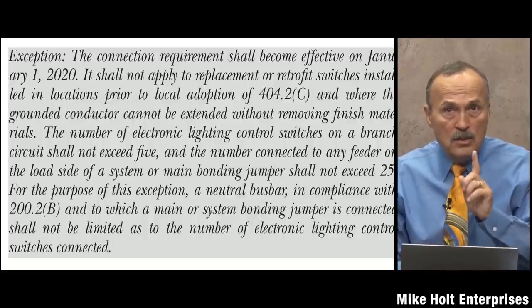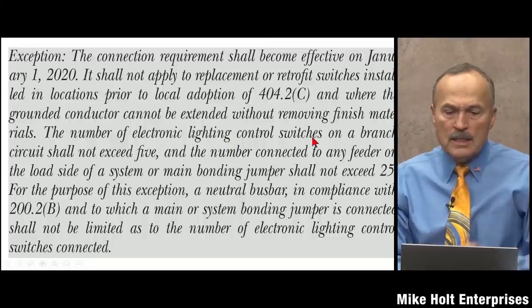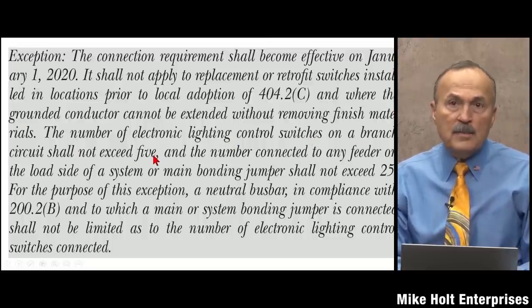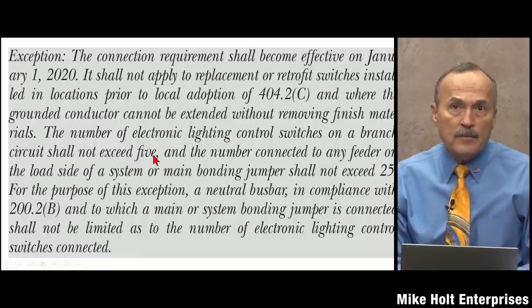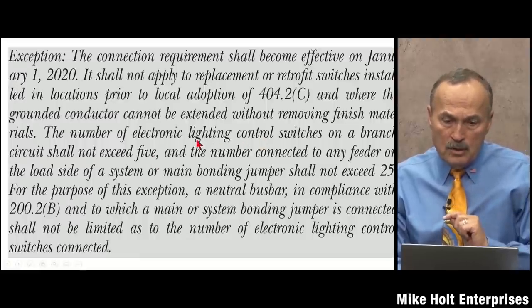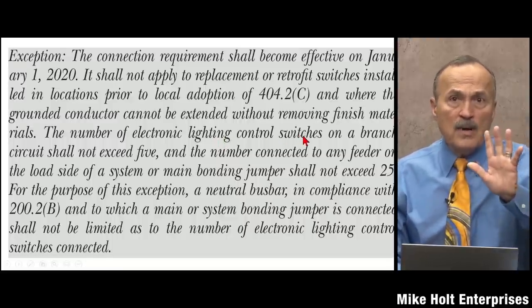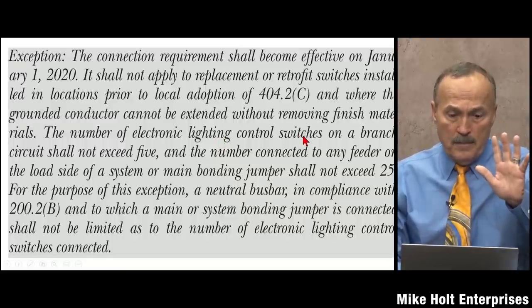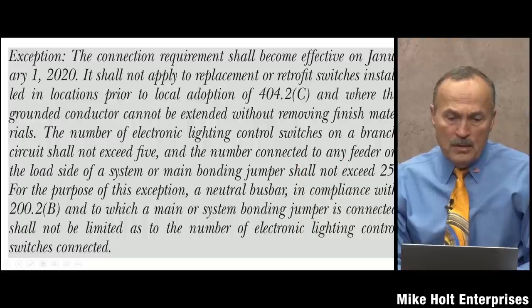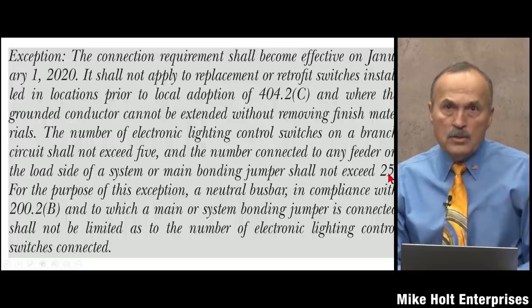However, there are limitations: the number of electronic lighting control switches on a single branch circuit shall not exceed five, and the number connected to any feeder on the load side of the system bonding jumper shall not exceed 25.